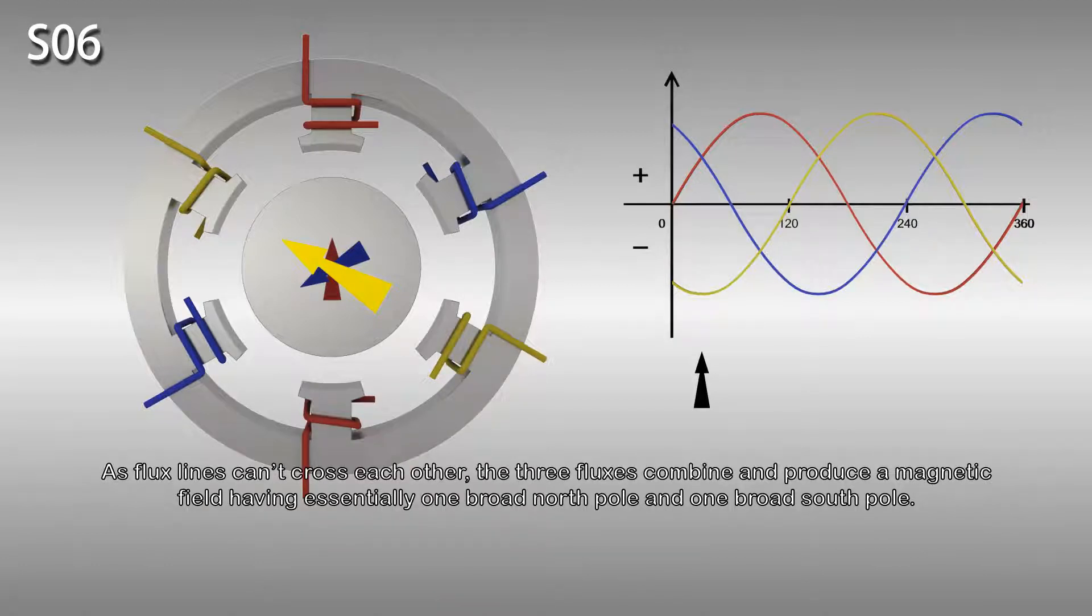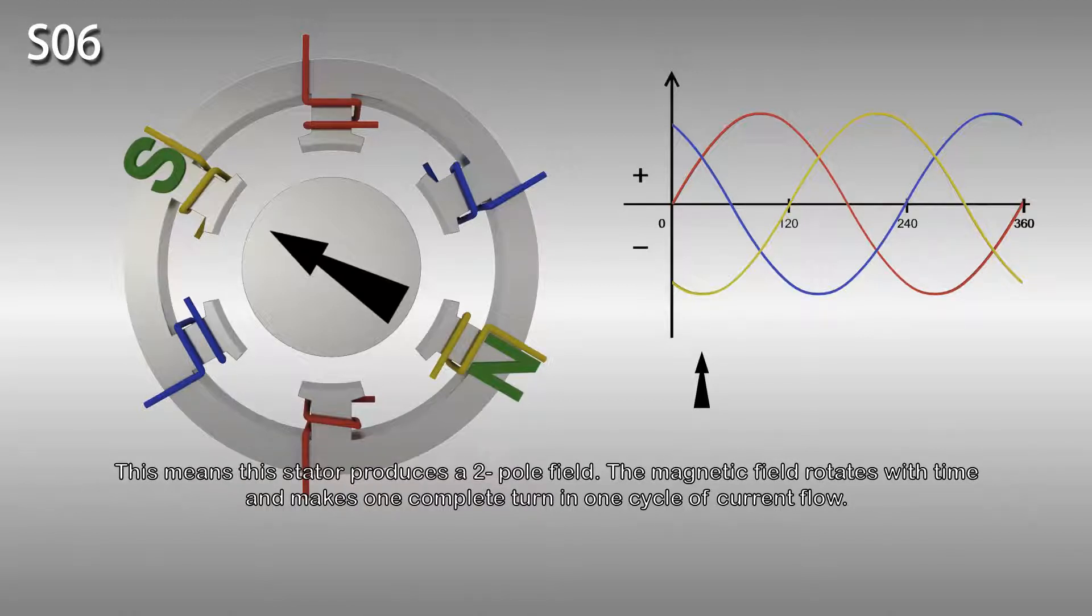As flux lines can't cross each other, the three fluxes combine and produce a magnetic field having essentially one broad north pole and one broad south pole. This means the stator produces a two-pole field. The magnetic field rotates with time and makes one complete turn in one cycle of current flow.